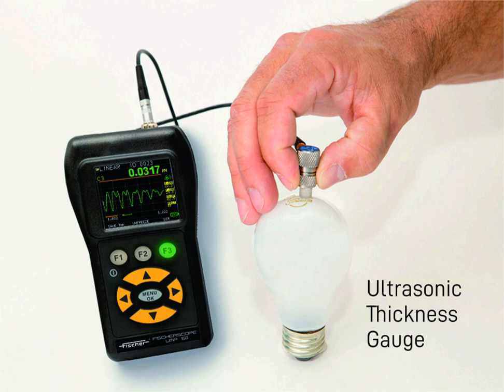Some ultrasonic coating thickness gauges require that a couplant in gel, paste or liquid format be used to eliminate gaps between the transducer and the test piece. One common couplant is propylene glycol, but there are many other options which can be substituted.